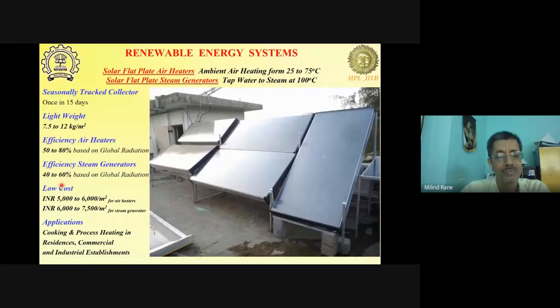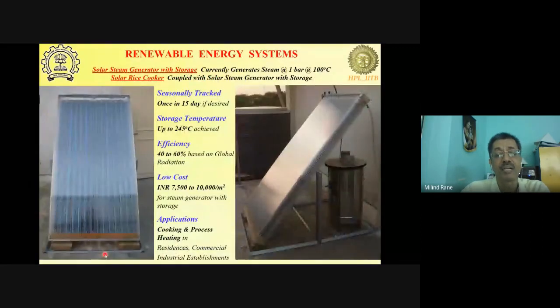At 1000 watt per meter square, we can easily get to efficiencies of around 60% for generating steam at 100 degrees centigrade. Okay, saturated steam at 100 degrees centigrade. The costs are low. The air heaters are much cheaper than the steam generators. And we can use these for cooking, baking, and various other residential space heating and other industrial heating requirements.